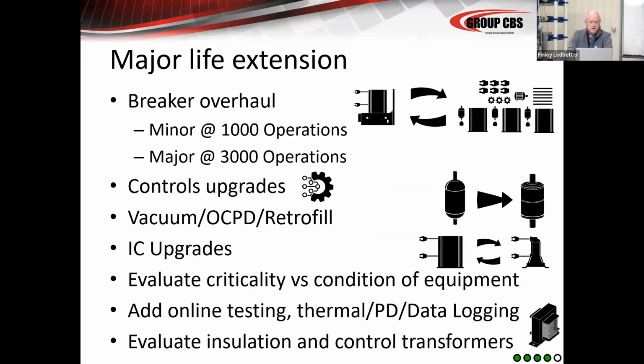Let's forge forward. Finley, along that line of accessories and other things other than the breaker, what about, and this is a question, what about the life of protection relays and trip units installed on the breaker? Well, if you look on this next page I just clicked to, every one says OCPD. That's the overcurrent protective devices. That's the relays. I know it says overcurrent, and a lot of these particular relays are voltage controlled, frequency controlled, differential schemes. There's all kinds of other situations in there. But basically, when I say OCPD retrofill, I'm talking about the controls, meaning any of the protective devices.